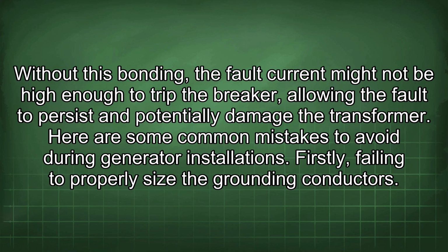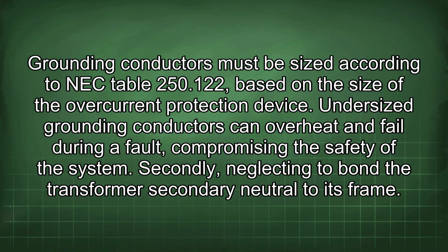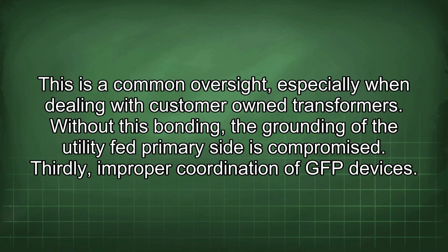Here are some common mistakes to avoid during generator installations. Firstly, failing to properly size the grounding conductors. Grounding conductors must be sized according to NEC Table 250.122, based on the size of the overcurrent protection device. Undersized grounding conductors can overheat and fail during a fault, compromising the safety of the system. Secondly, neglecting to bond the transformer secondary neutral to its frame. This is a common oversight, especially when dealing with customer-owned transformers. Without this bonding, the grounding of the utility-fed primary side is compromised.